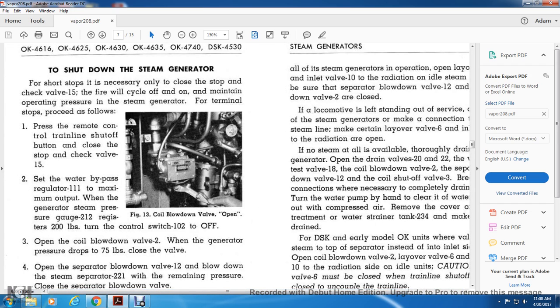Alright, to shut down the steam generator. For short stops, it is necessary only to close the stop and check valve 15, but the fire will cycle off and on and maintain operating pressure in the steam generator. For a terminal stop, proceed as follows. Press the remote control train line shutoff valve button and close the stop and check valve 15. Set the water bypass regulator 111 to the maximum output. When the generator steam pressure gauge 212 registers 200 pounds, turn the control switch 102 to off.